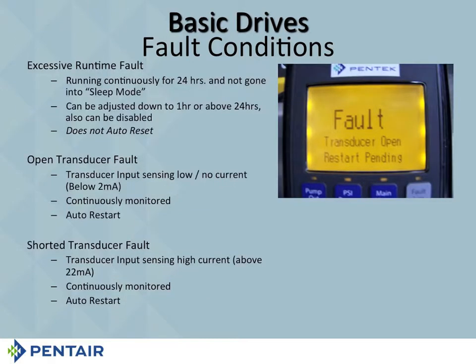Now, the next one we're going to talk about here is excessive runtime fault. What that simply means is that the drive has not gone to sleep in 24 hours. If the pump isn't going to sleep in 24 hours, it could mean a broken pipe. It could mean something else is going on. You're always using water, and you need to know that. So that's all it's going to do. It's set for 1 hour, but you can set it for anything you want to.